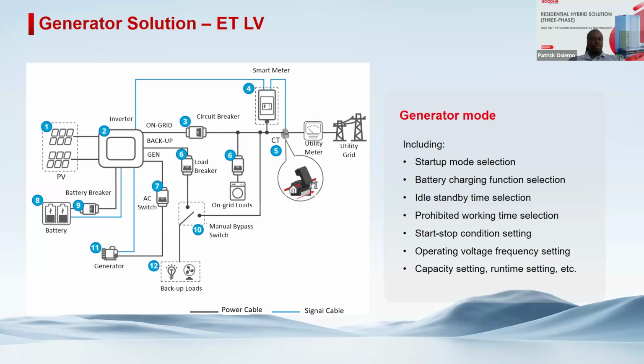You can choose what times to start, what time to stop. You can choose the operating ranges of the voltage or even the frequency that the generator is outputting, because the diesel generator outputs depend on the age and the maintenance schedule that's done on the generator. So with the aging of the generator, you can still adjust these acceptable voltage or frequency ranges. You can also select the capacity of the generator connected to the inverter itself. So we have a very smart way in which you can integrate your diesel generator to the ETLV itself.